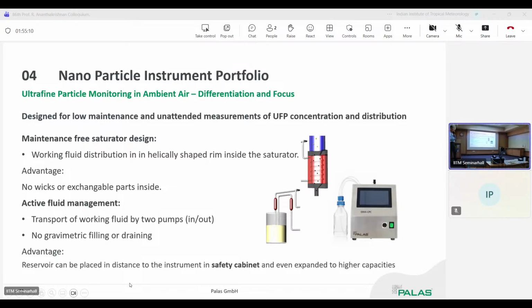Specifically, what do we do differently from what others typically do? We have a maintenance-free saturator design. This is the saturator. It has a helical shape, and inside the helical shaped area the butanol flows through and is evaporated by heat. And we have active fluid management, which means we pump butanol into the saturator, but we also pump it back to the reservoir. With that, we can place the bottle a bit farther away, not directly on the device, maybe also in a safety cabinet, if you see that as a requirement, especially if you use reservoirs of more than 1 liter. So you can use reservoirs of 2.5 liters or 5 liters, for example, place them in a separate cabinet, and then hoses go to the CPC and manage the fluid.